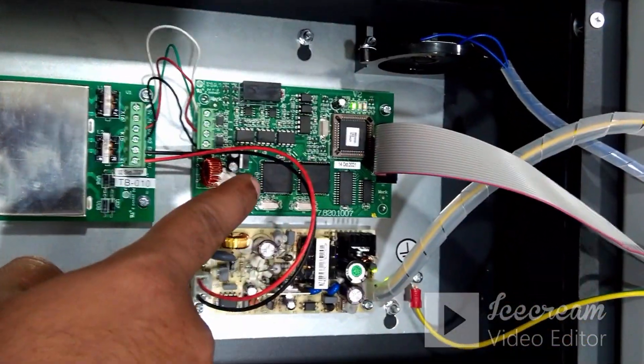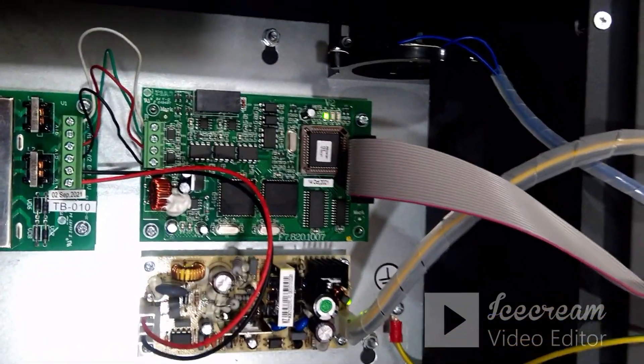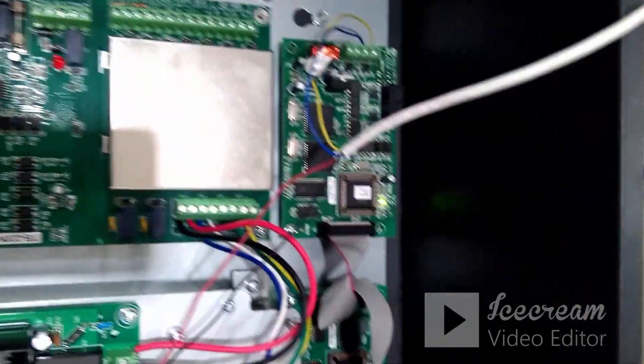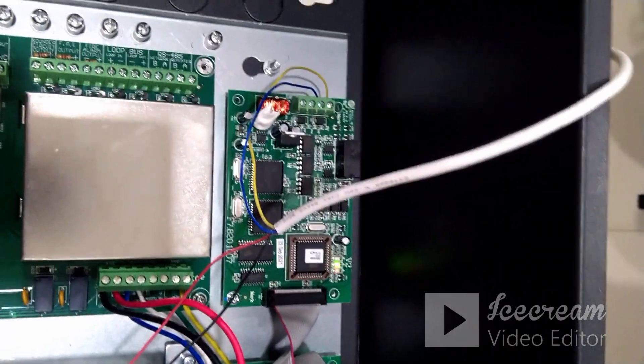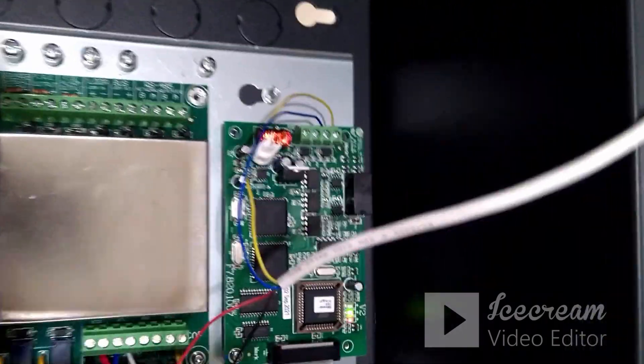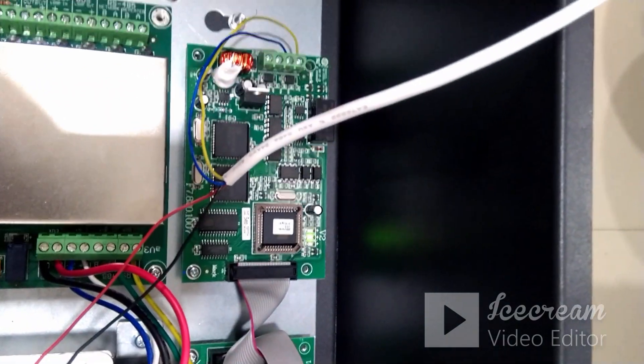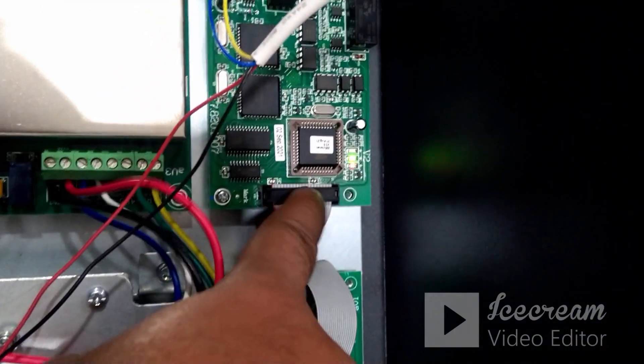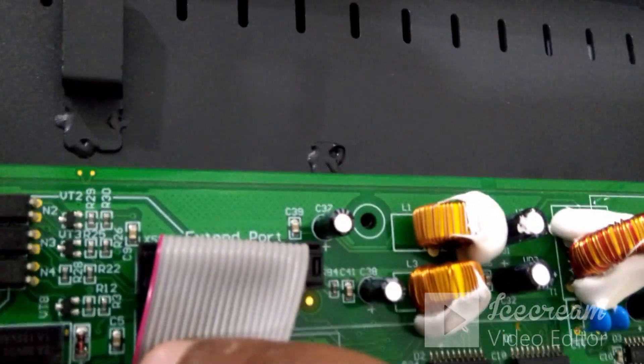These two slots will normally be free so we can connect this card. The part code of this particular card is P9940A. The first step is to get the card and place it on the location where this slot is on the panel. The card comes along with a ribbon cable — you can connect this ribbon cable to the panel. The port is the Extend Port.